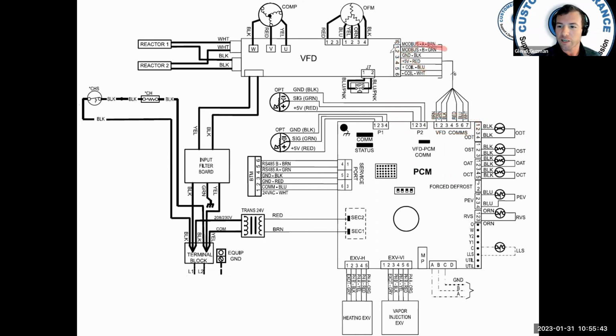Now, if you've disconnected this plug, okay, it's pulled off, and I don't have the 5 volts DC here, then what I want to do is start checking these sensors. Okay, check these sensors and see, are any one of them shorted? Hopefully you would have a shorted sensor fault. But if you don't, you could start pulling the sensors off and see, does my voltage come back? You know, if I pull off one of these sensors and all of a sudden, hey, I got voltage, well, I probably got an issue with that sensor, okay?